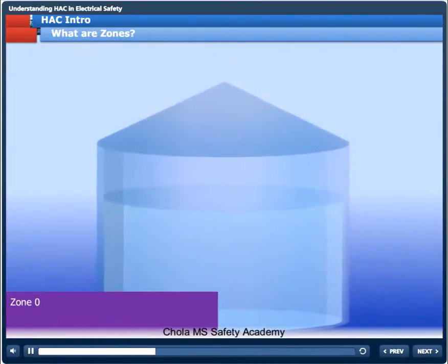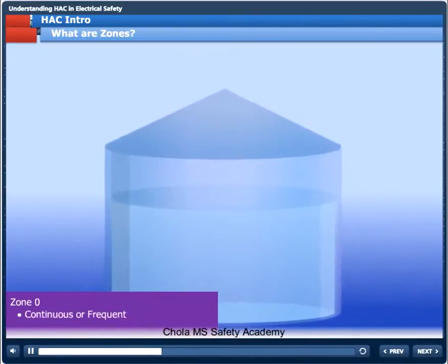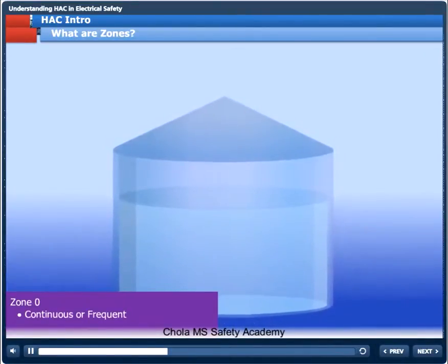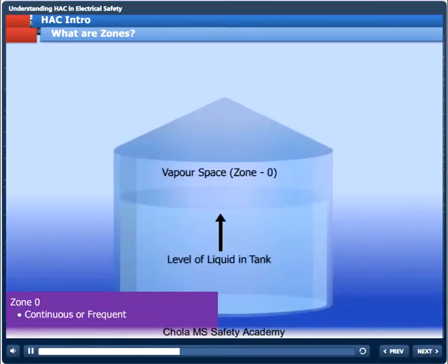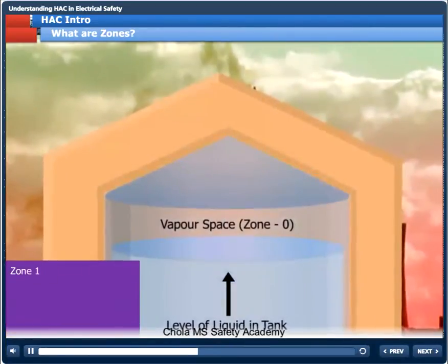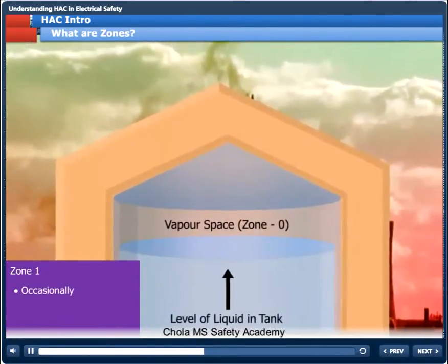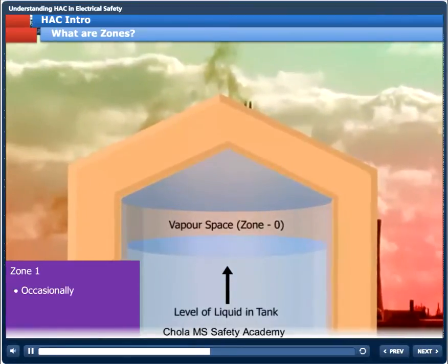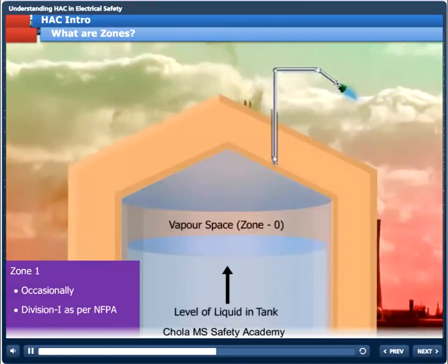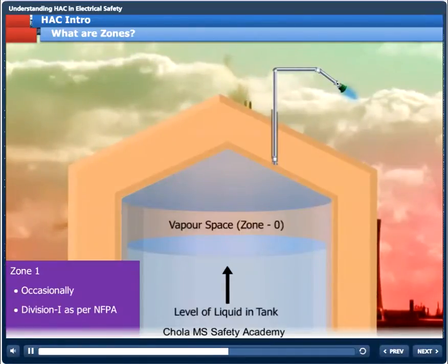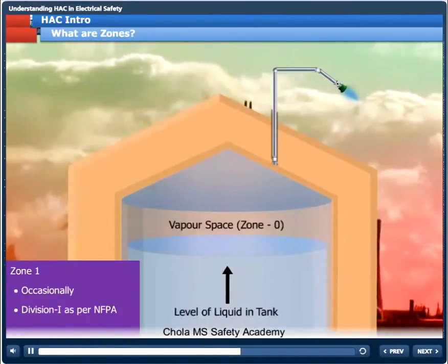Zone 0 is an area in which an explosive gas atmosphere is present continuously, or for long periods or frequently. For example, inside of a tank or container containing flammable liquid that has continuous presence of flammable vapor. This zone is synonymous to Division 1 as per NFPA standards. Zone 1 is an area in which an explosive gas atmosphere is likely to occur in normal operation occasionally. For example, the space around the vent of a tank holding flammable liquid may have a flammable vapor around it occasionally. As per NFPA standards, both the zones, for example, Zone 0 and Zone 1, are represented by Division 1 only.